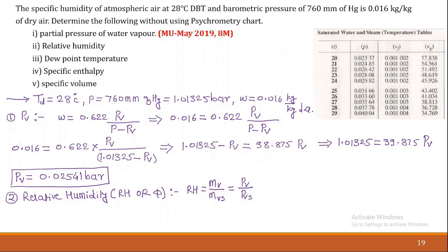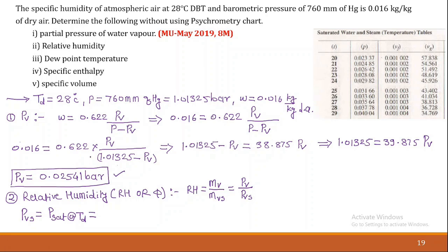To find RH we need Pv and Pvs. Pv is already calculated as 0.02541 bar. Pvs is the saturated pressure at the dry bulb temperature of 28°C. From the steam table at 28°C, the saturated pressure Pvs = 0.03778 bar.